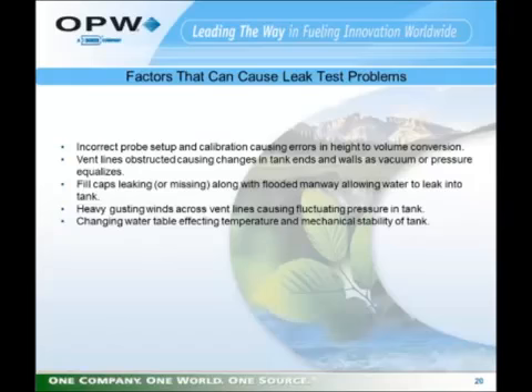Factors that can cause leak test problems are incorrect probe setup and calibration. An accurate test is incumbent upon the tank properties being properly input into the tank gauge. We must know the correct tank size, shape, volume, and product, and the probe setup must use the correct settings for the probe, and the probe must be calibrated properly.